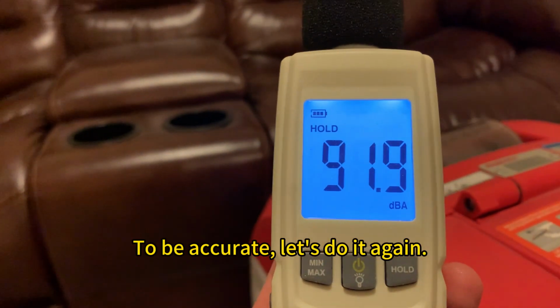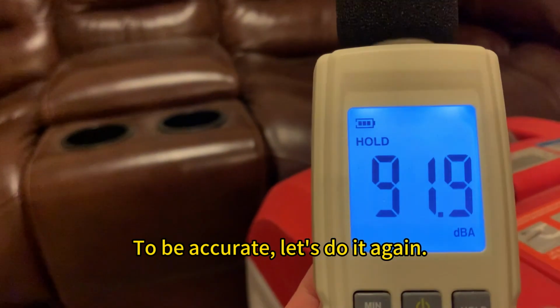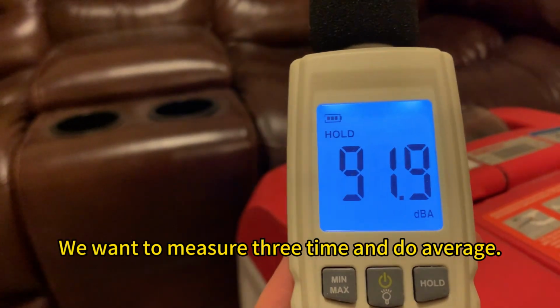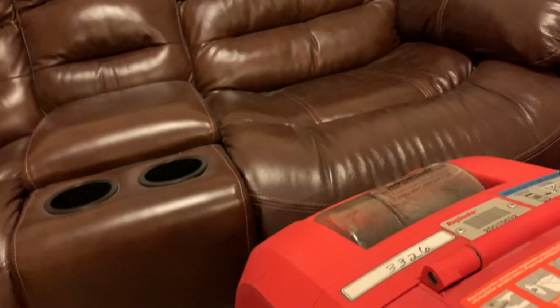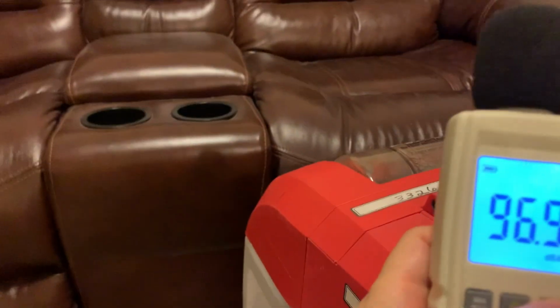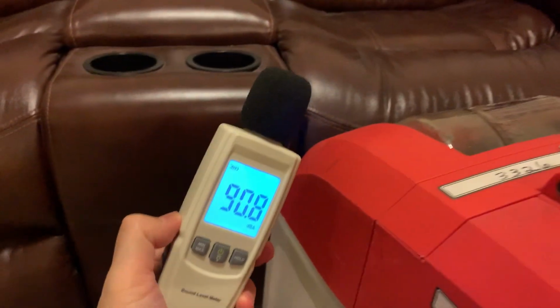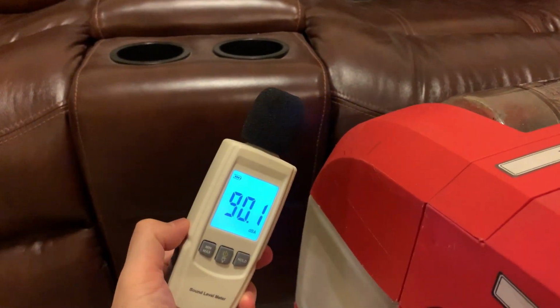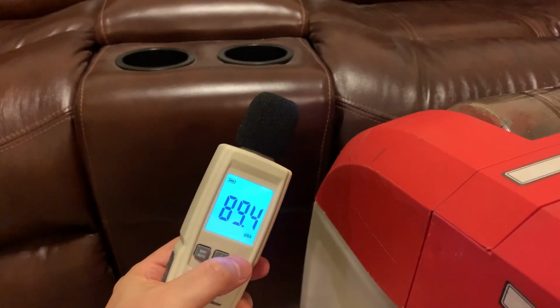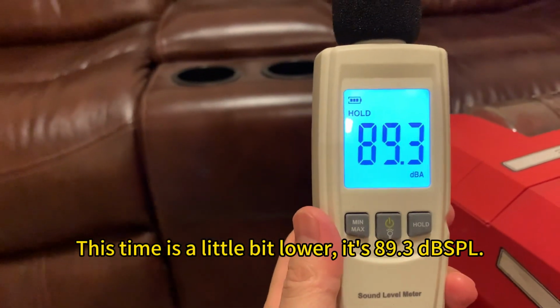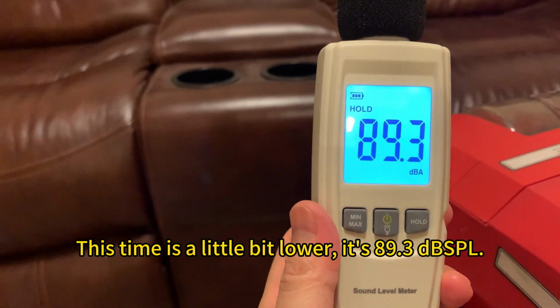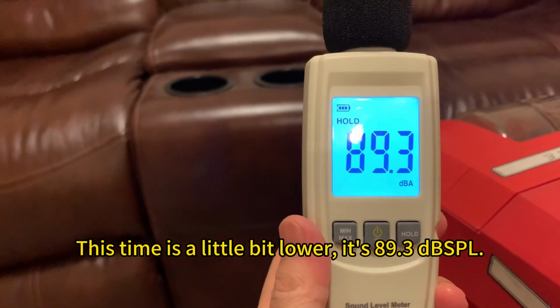Okay, so to be accurate, let's do it again. And we want to measure 3 times and do average. So this time is a little bit lower. It's 89.3 dBSPL.